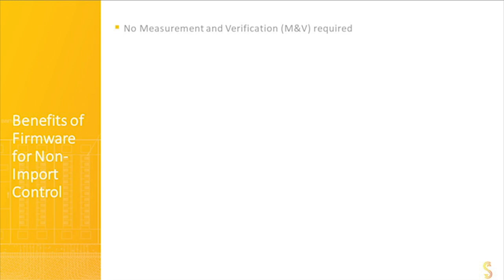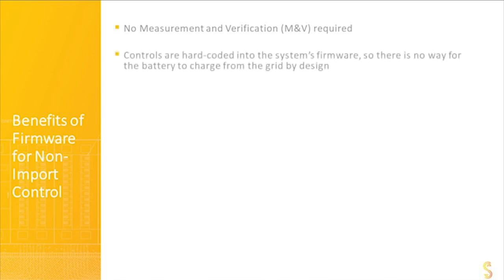With DC coupled systems, guess what? Every electron that goes into the battery necessarily came from the solar by design, as tested and verified by UL. So absolutely no measurement and verification. This thing works by design. You don't have to check it. You don't have to measure it. It's done. That's pretty incredible, and that's unheard of right now. Again, the controls are hard-coded in the system's firmware, so there's absolutely no way to break this. This is hard-coded in, verified by UL, never going to change. Good for 20 plus years.